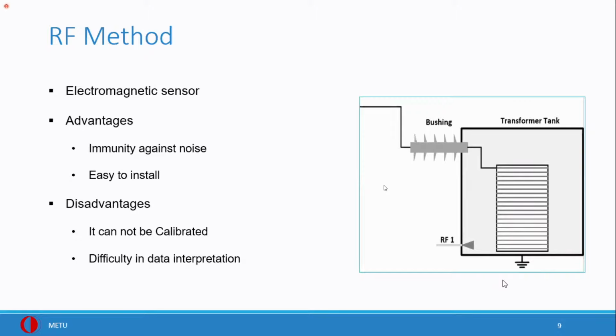The only type of fault that can go as high as 1 gigahertz is the partial discharge generated by this impurity. So by measuring at these higher frequencies, we get rid of this noise.